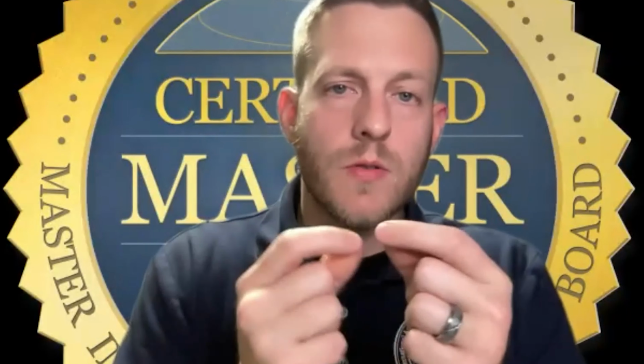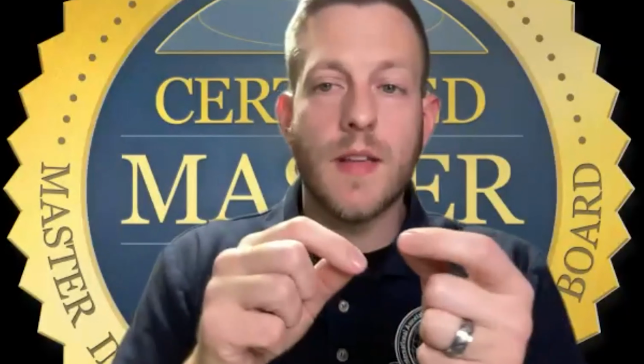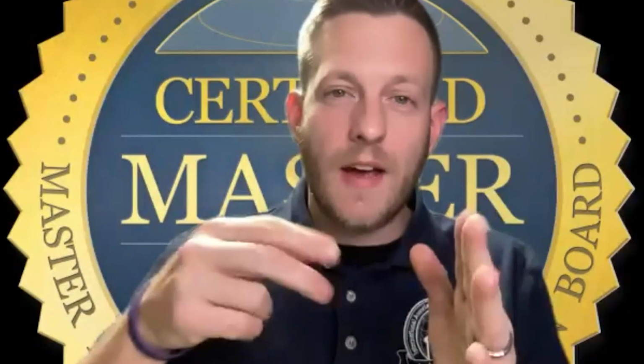When it's open neutral, it means it's non-secured. What does that mean? On an outlet, you've got terminals on the back: a hot wire coming in, a neutral, and a ground. Usually an open neutral means that at some point between that connection and the panel, that wire has come loose somewhere, most often at the actual outlet. I've seen outlets called backstab, where the conductor goes into the outlet and you don't have to wrap it around and screw it. It just fits in like a shark bite connection, and they've come loose at some point.